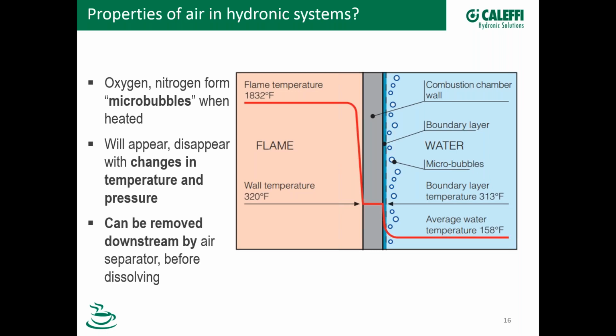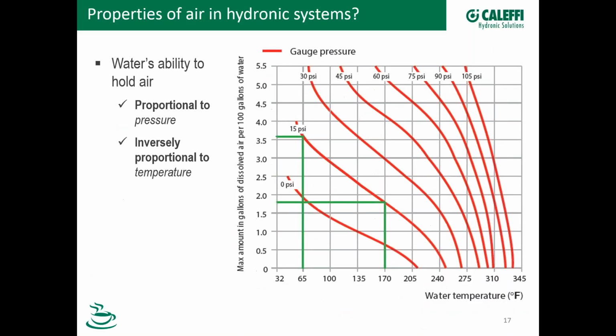Now these bubbles can be removed downstream by an air separator before they dissolve back into the fluid. So as those bubbles form, what we need to do is remove those from the fluid before they then get redissolved back into the fluid. Here's a graph that we like to use. This shows the water's ability to hold air.